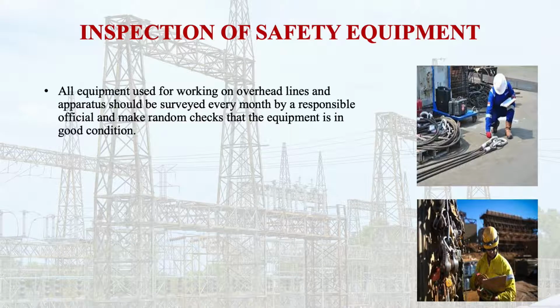So let us begin with the inspection of safety equipment. We state here the safety procedures for the inspection of equipment. All the equipment used for working on overhead lines and apparatus should be surveyed every month by a responsible official, and he or she should make random checks on the equipment to satisfy themselves that the equipment is in good condition. So this checking is required.